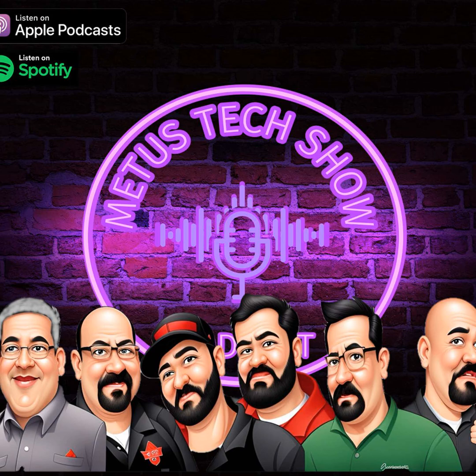Today's METUS Minute is about system additives. From the factory, a Mitsubishi heat pump system is shipped with the recommended oil and refrigerant for the particular model. Oil and refrigerant should be the only two chemical substances in our systems. METUS strongly recommends against using any additive or sealer in our HVAC systems due to the possibilities of causing restrictions.